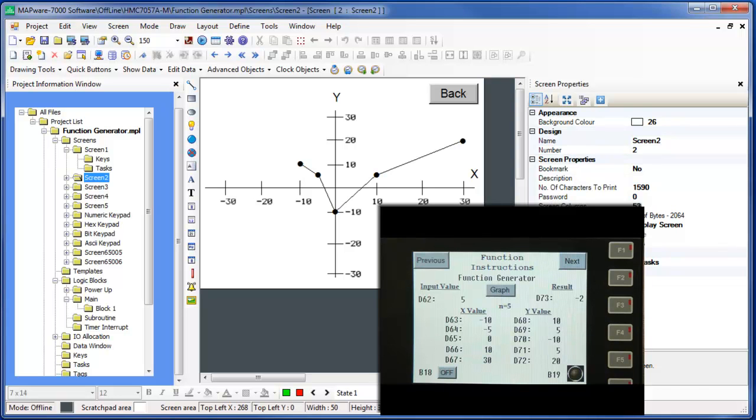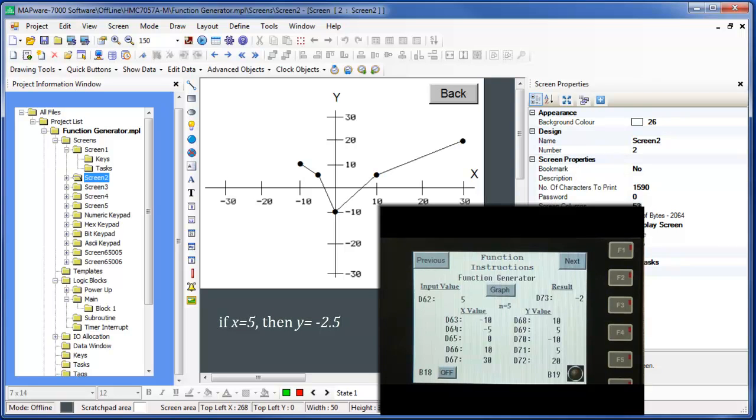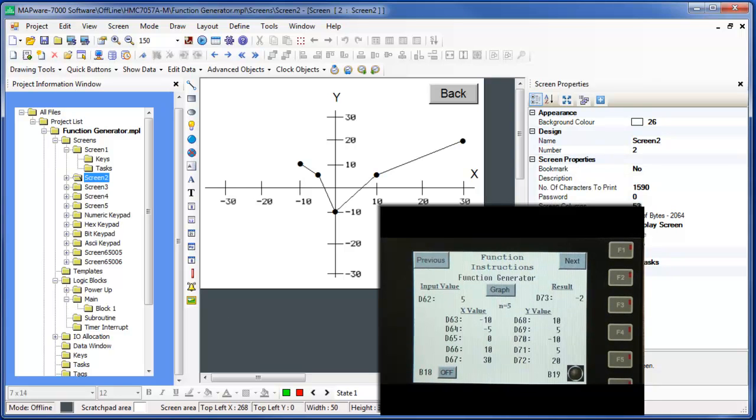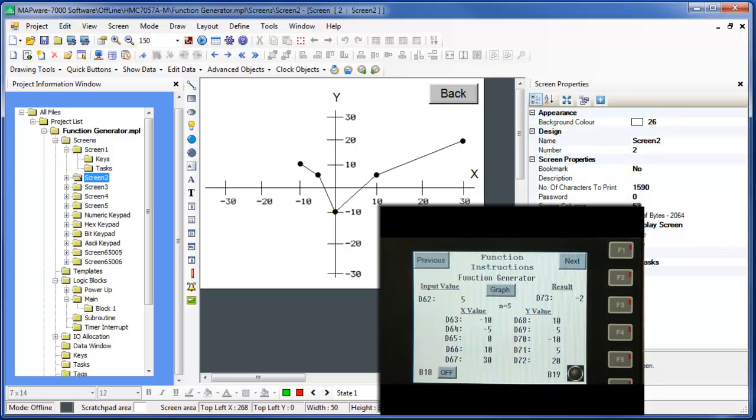If we were to calculate the value of Y using simple algebra, we would get a value of Y equals negative 2.5 for an X value of 5. So why do we not see this value here? Remember that the function generator performs all calculations using integer math. So any decimal value will be truncated to a whole integer value. In this case, negative 2.5 is truncated to negative 2.